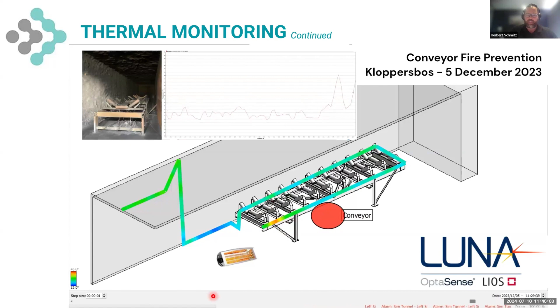Here's a real world incident. This was at a coal terminal in Mozambique. The technicians were commissioning the fiber optic sensing system, so they were heating up the beginning and the end of each of the conveyors. And when they looked at the temperatures, they saw the spike on conveyor 11. And when they investigated, they saw that the pulley was building up frictional heating against the spillage.